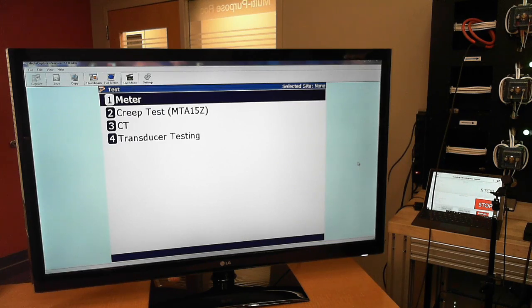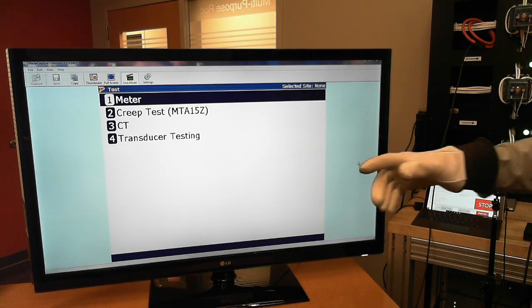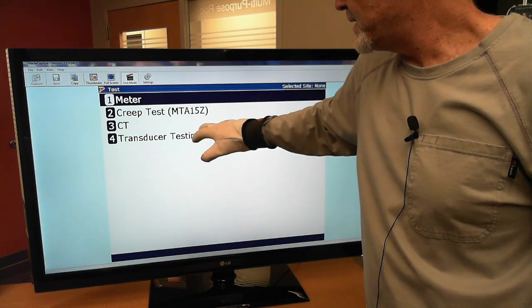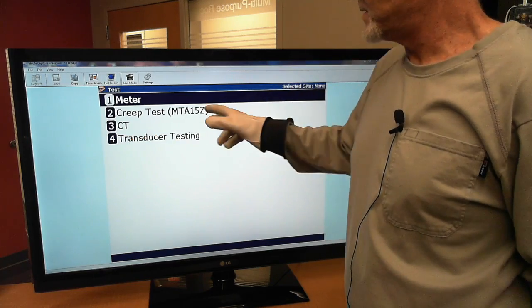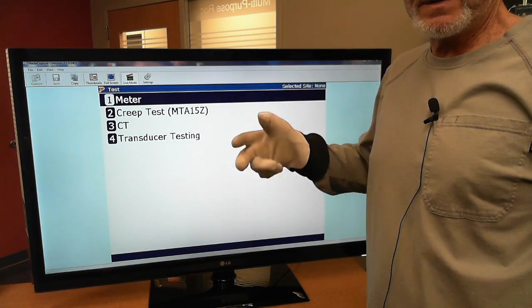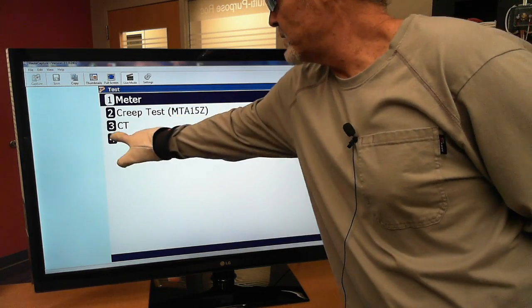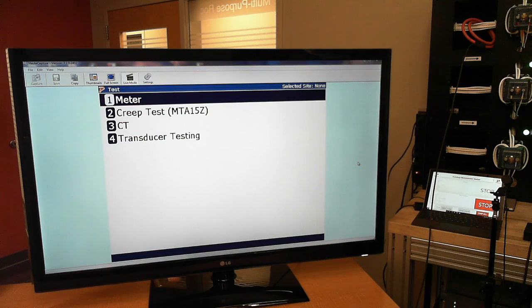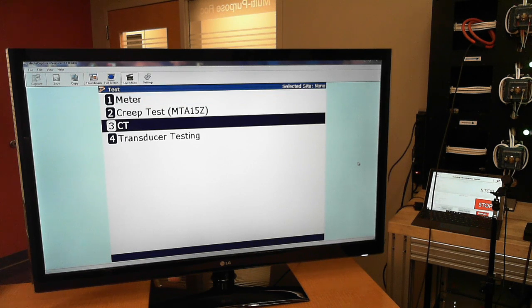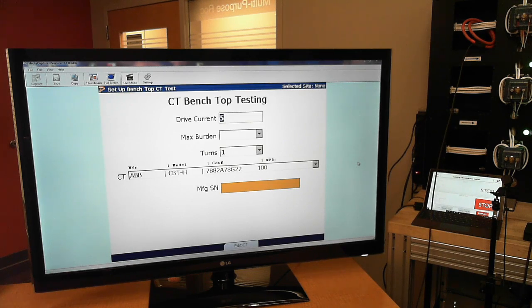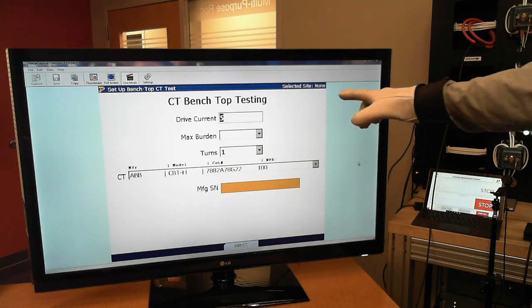Now it gives me choices—these are different component tests I can do. I can do creep tests on a meter, I can do transducer testing. These are some of the options of component testing with the 7 series. But the one we want is number 3, a CT test. So you can see it's going right to the CT benchtop test, which is what we want to do.